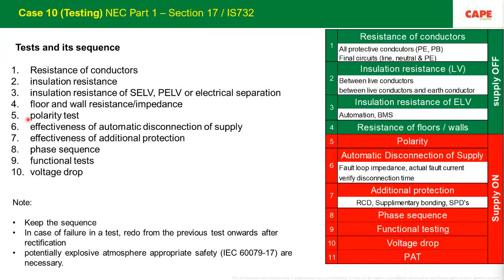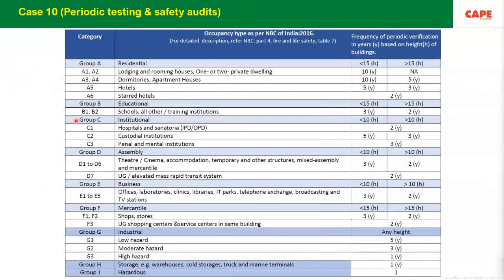The last one is, I would say, the testing of an electrical installation. There are 10 tests. Of course, there is one more, which foreign countries started doing, called PAT, Portable Appliance Test. These 10 tests, or at least the 10 tests, are made mandatory in the regulations or the standards. But unfortunately, you have to be careful and you should do this. So case number 10 is testing of the electrical installation, also the periodic testing. In periodic testing, you probably don't need to do all the tests, but some of the tests are mandatory.